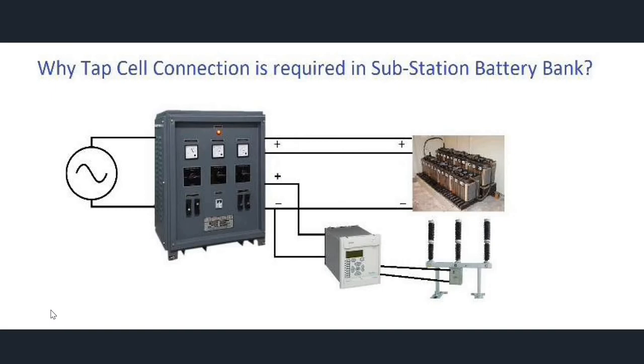There are different sets of battery banks available in substations for communication systems as well. In a battery or battery bank, generally we know there are two terminals — one positive and one negative — but in a substation what we observe is that there are three connections given to a battery coming from the charger. Why this third connection is used, and how it is connected, we'll see from the block diagram. It can be observed that an AC source is connected as input to the charger and the output of the charger is connected to batteries as well as the relays and circuit breakers, which are considered the DC loads for the substation.